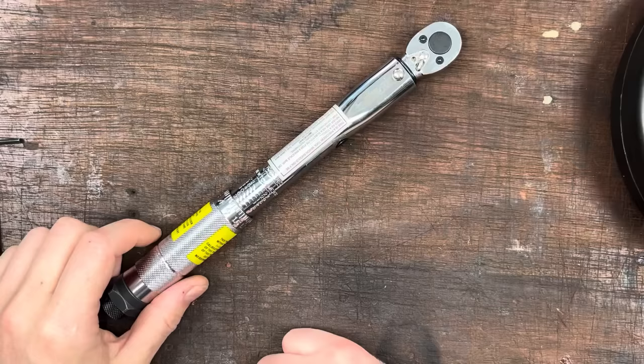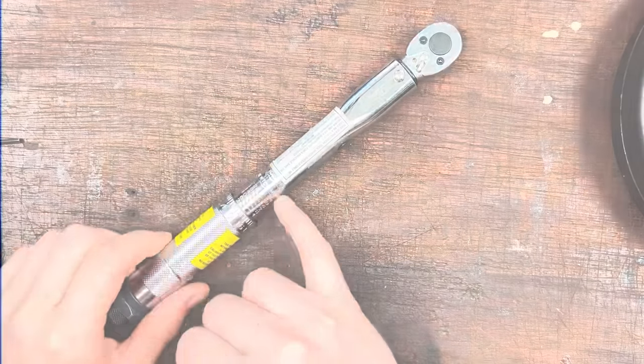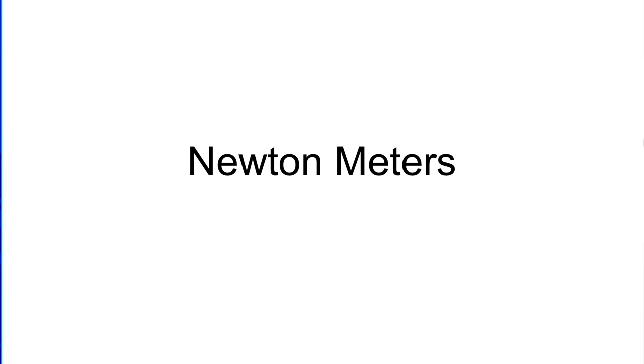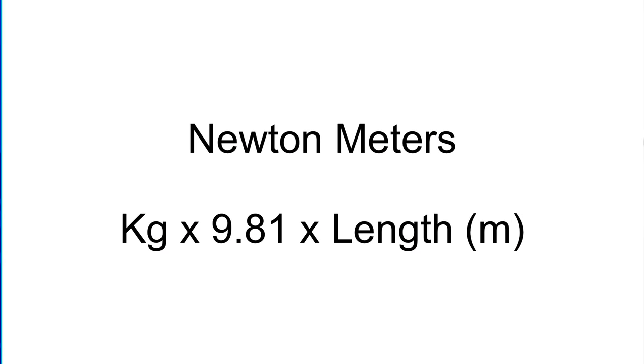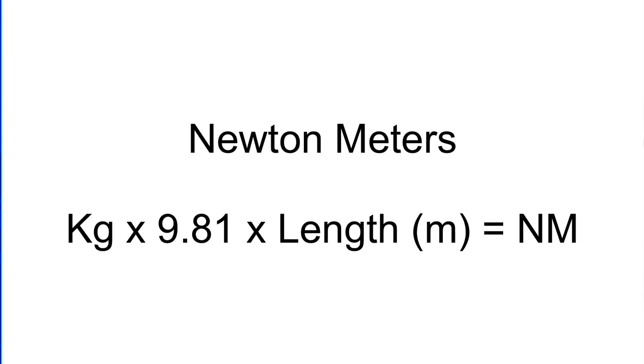So we need to know a very simple equation. Please don't get hung up on it, it really is simple, don't look into it any further than you need to. If we're working with a metric torque wrench, which will be in newton meters, we need to use the equation weight in kilos times by 9.81 times by the length in meters, that will give us newton meters.